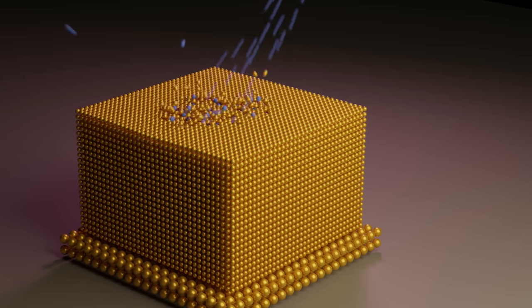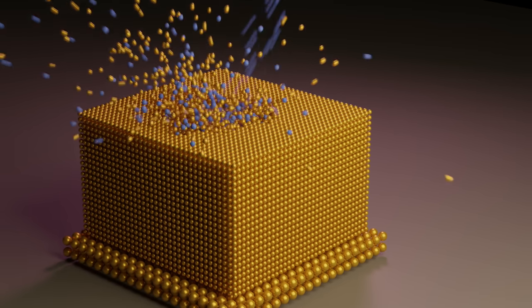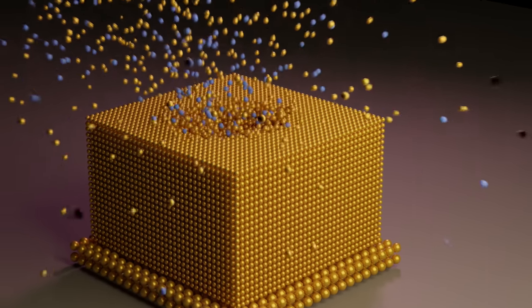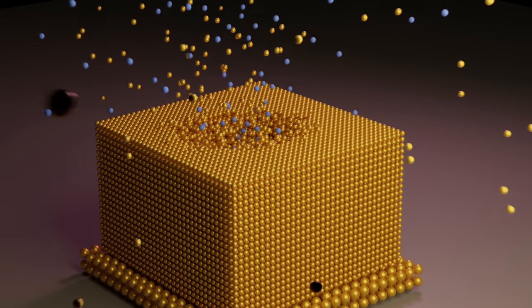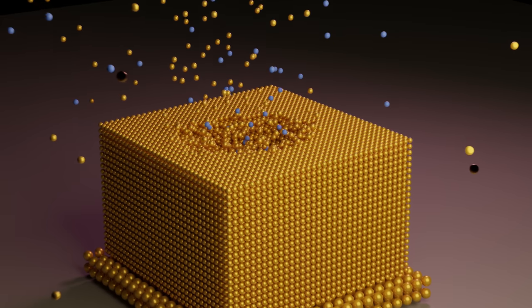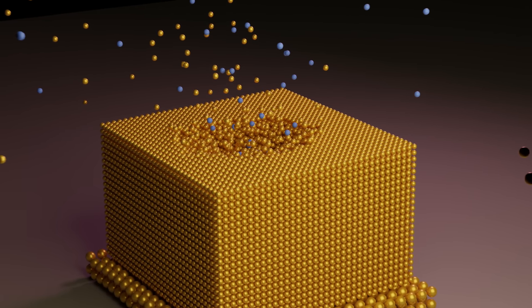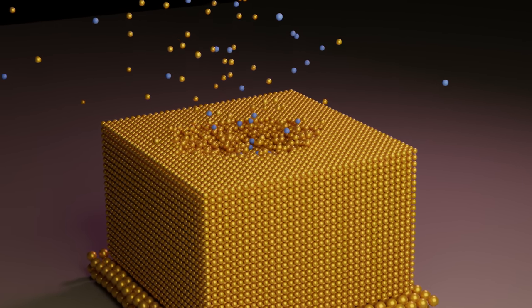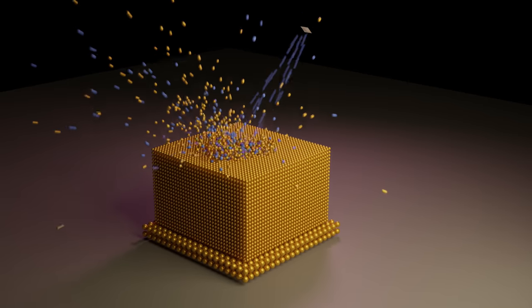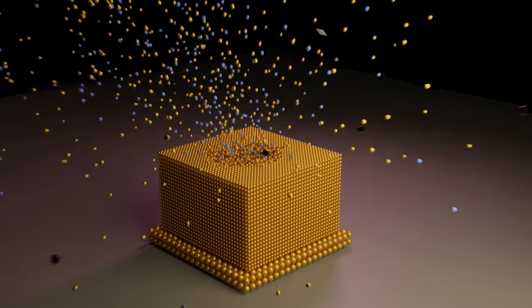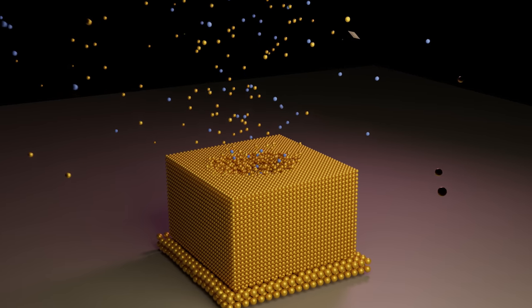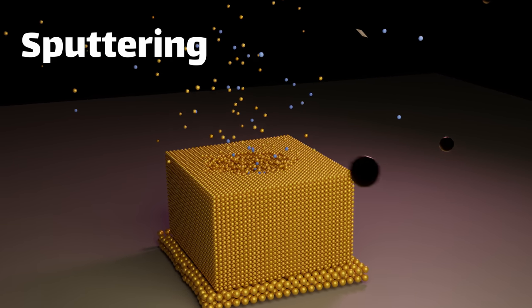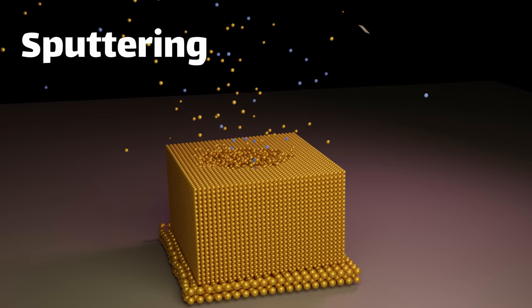The argon particles are in blue and the sample is in yellow. As the argon hits the surface, we can see a few things happening. First, the argon either bounces off without doing anything, bounces into the interior of the sample and gets stuck there, or it knocks free an atom of the sample. Over time, and with enough argon impacting the surface, a small crater is formed. This process is known as sputtering, and it's basically how we etch the surface of the sample.